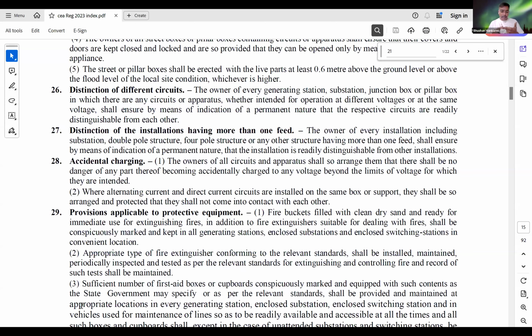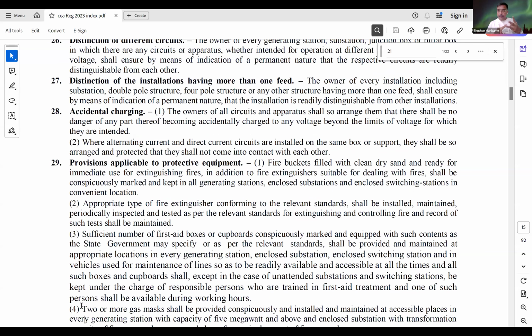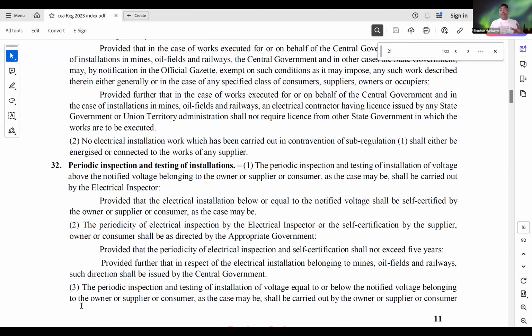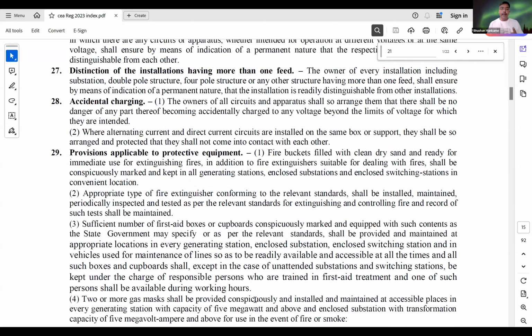They don't have a helmet. They don't have HT gloves. They don't have safety shoes. And there's no wooden ladder to help him in case of emergency. There's no provision of fall protection. Sometimes the electrical shock is very minor, but the fall of the line staff makes more impact on his body and leads to non-fatality or fatality. So these are the simple provisions which are already elaborated in Regulation 21, which should be implemented at DISCOM level to avoid these accidents.